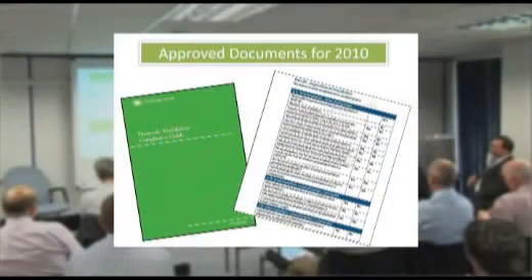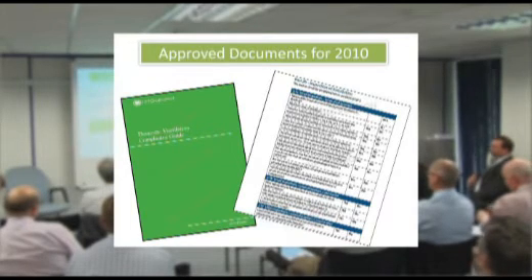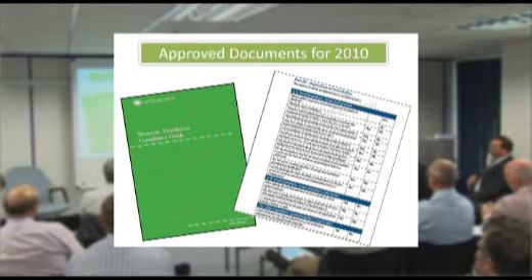You guys will probably never actually see that document, but because of the failures previously, CLG have now insisted that a domestic compliance guide is set up for mechanical ventilation installations. As part of that, your work and your installations are going to be checked by a third party. The guys fitting the mechanical systems cannot sign off their element — the balancing of the mechanical ventilation systems and the extract fans in the bathrooms — without checking your work. If your work is incorrect, you will be coming back to do remedial works to those properties. It is very important that you check your background ventilation systems.